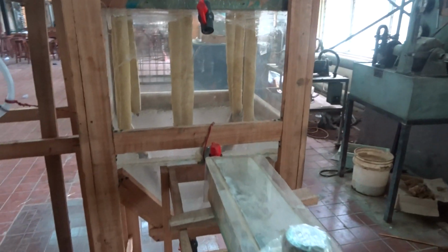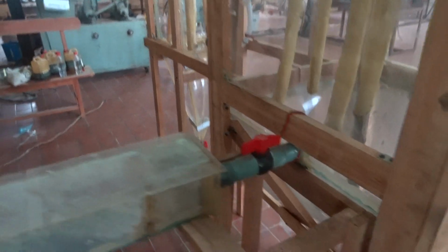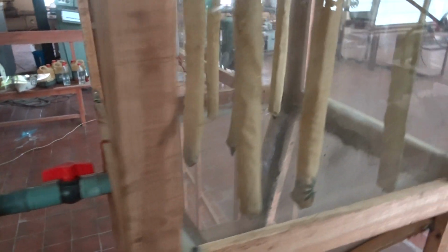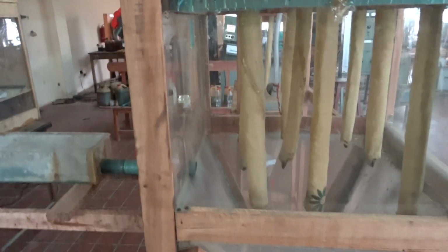However, over time, the pores of the filter bag will be blocked as a result of continuous bombardment of the walls of the filter bag by the particles of the particulate, trapping and attaching themselves to the walls, and that will reduce the efficiency of the whole setup.